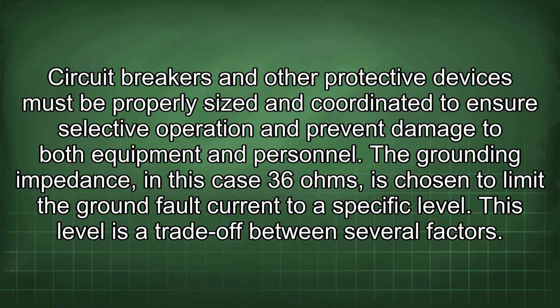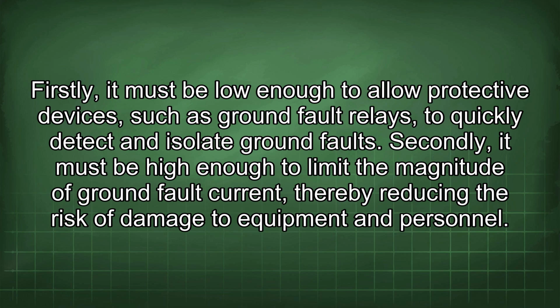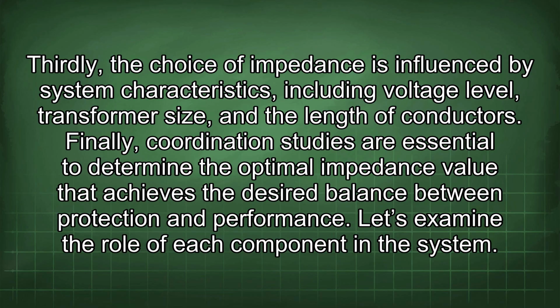The grounding impedance, in this case 36 ohms, is chosen to limit the ground fault current to a specific level. This level is a trade-off between several factors. Firstly, it must be low enough to allow protective devices, such as ground fault relays, to quickly detect and isolate ground faults. Secondly, it must be high enough to limit the magnitude of ground fault current, thereby reducing the risk of damage to equipment and personnel. Thirdly, the choice of impedance is influenced by system characteristics, including voltage level, transformer size, and the length of conductors. Finally, coordination studies are essential to determine the optimal impedance value that achieves the desired balance between protection and performance.